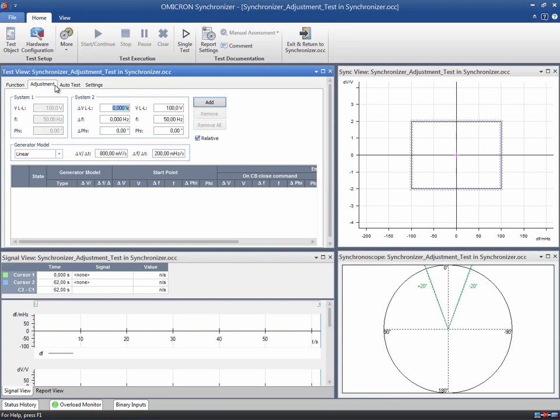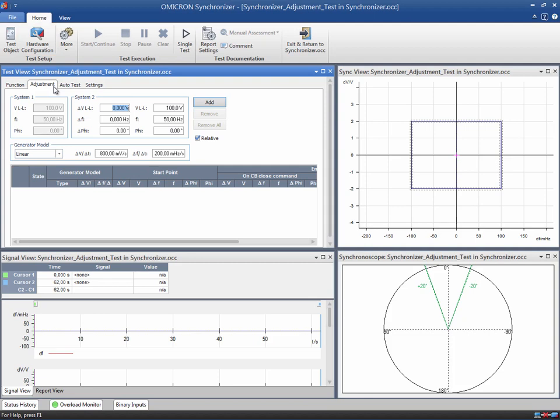This test allows us to check the actuator commands issued from the relay to the generator. Do not forget to check the local hardware configuration to ensure that all signals are enabled. The principle behind the operation of the relay is to bring the generator into synchronization by means of the voltage and frequency control commands.